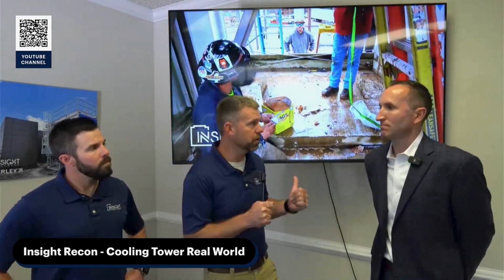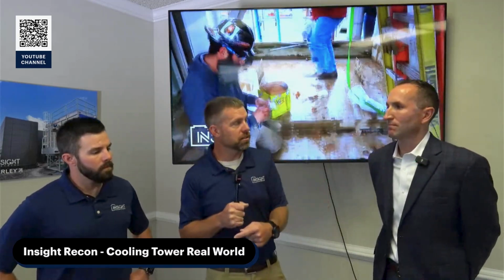If it's a 78 degree wet bulb design day and they say, well, I need 75 degree water, it's like, we can't do that. It's theoretically impossible. So figuring out the times of the year, because they could say, well, during the winter I was getting this. Well, now it's 90 degrees outside. Just making them understand how the equipment operates so that we can troubleshoot if there is a problem.